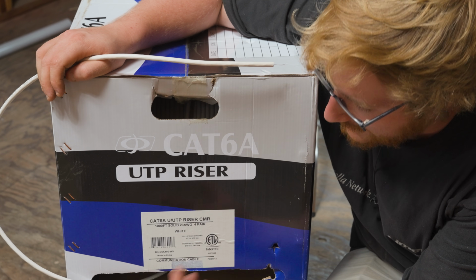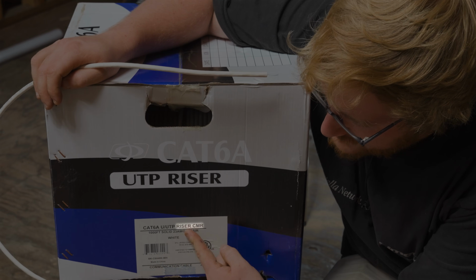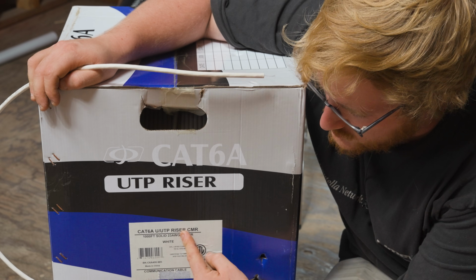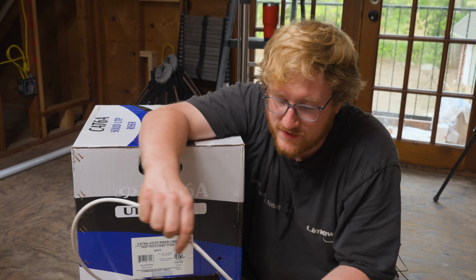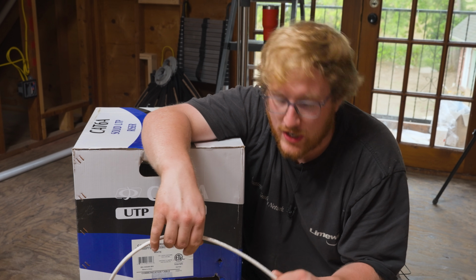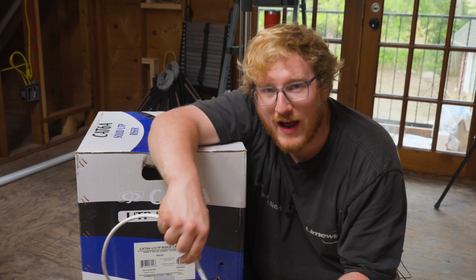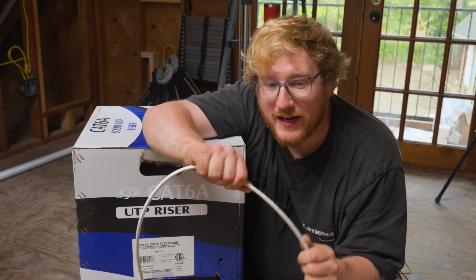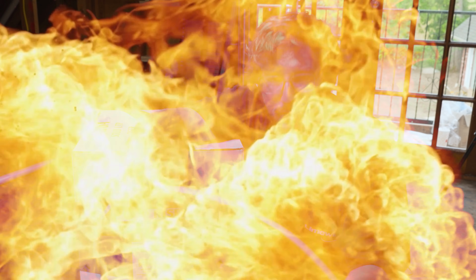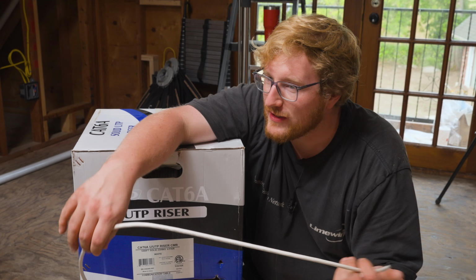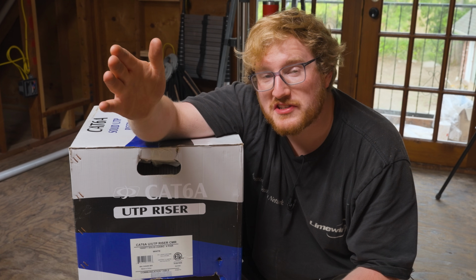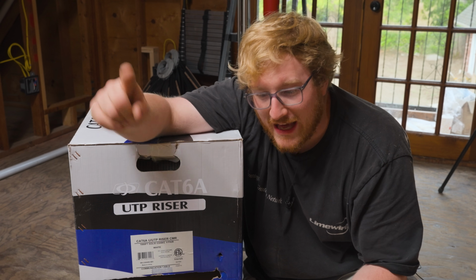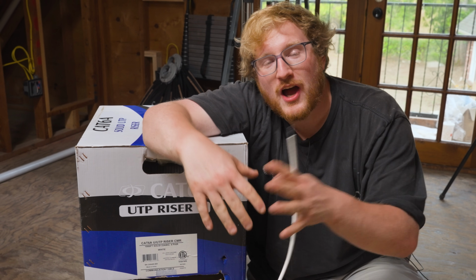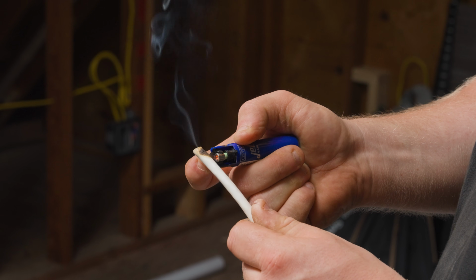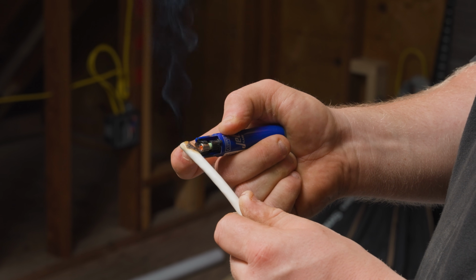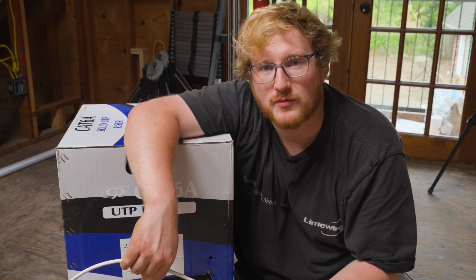If you're shopping for cable, you might also see something like Riser CMR or Plenum CMP. The main thing is if you're permanently installing the wire, generally to be code, you need riser spec wire. That's the fire rating, so this stuff doesn't just implode into a giant fireball. If you're running cable through the ventilation system in your house, you need plenum, because that insulation doesn't turn into toxic fumes when it burns. This stuff does, but toxic fumes and not fireball is good enough for inside the walls where you don't generally breathe.